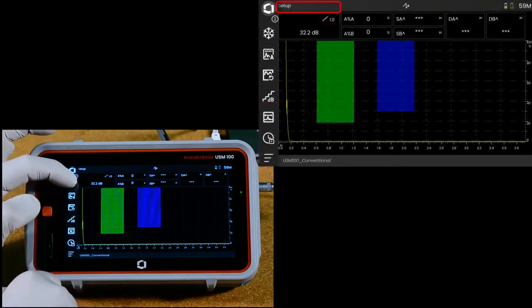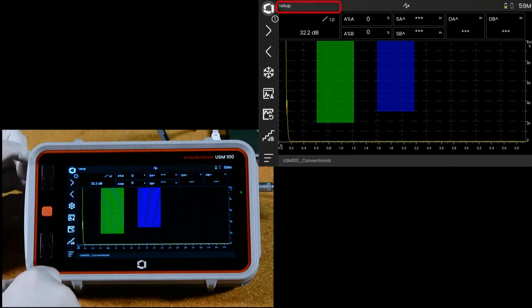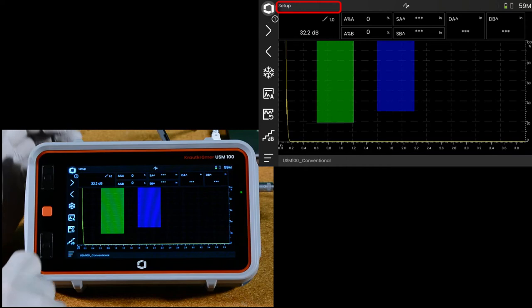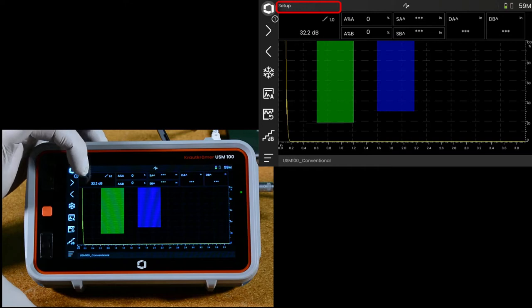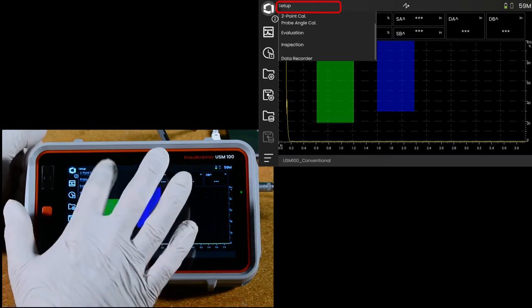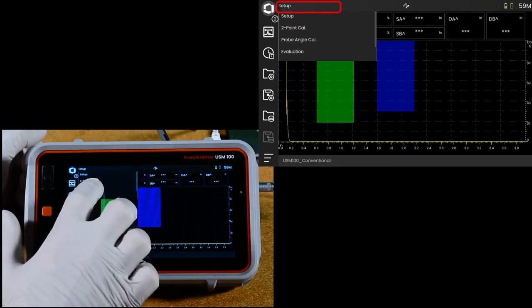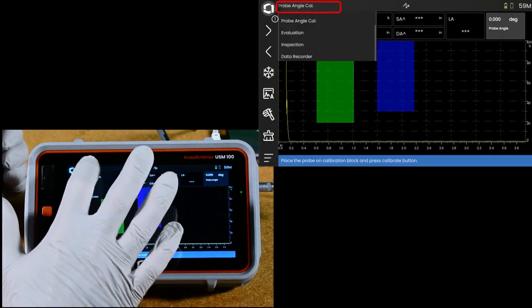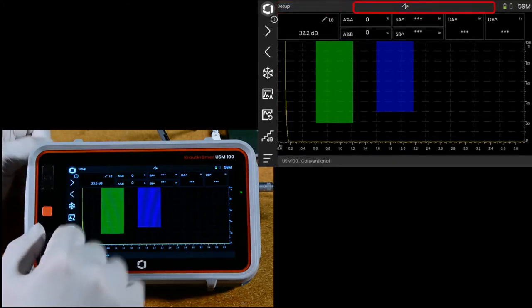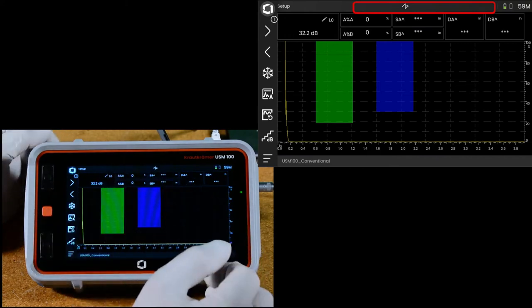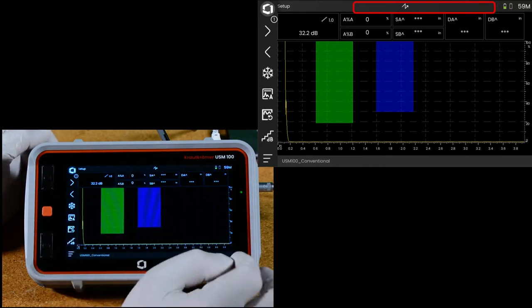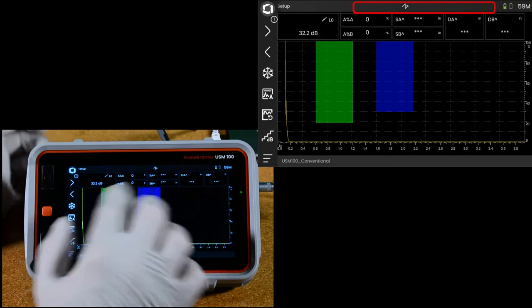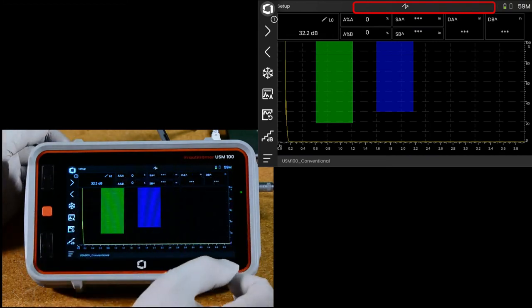The other icons we can go into in another video. The next special feature, we'll just kind of go around the instrument clockwise and spiral inward. Up here on the top status bar on the left hand side is a drop down where you can change panels of the app directly. So this app has five or six panels. If I wanted to go to the probe angle calibration, I would just touch that one and it will take me directly to that panel of the app. I can do the same thing and go back to my setup. Going across, there's an area for icons that indicate status or state within the instrument. We haven't done any calibration so far, so the only icon showing up there right at the moment is the icon that indicates I'm in pulse echo mode. If we were to go to the pulse receiver menu, turn dual mode on, that icon would change to indicate dual mode.